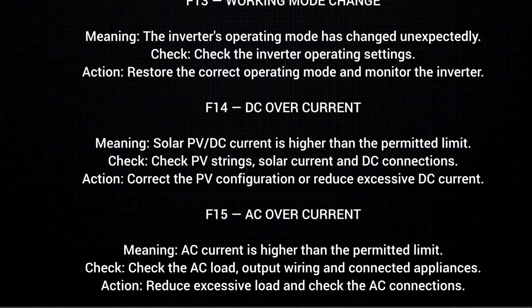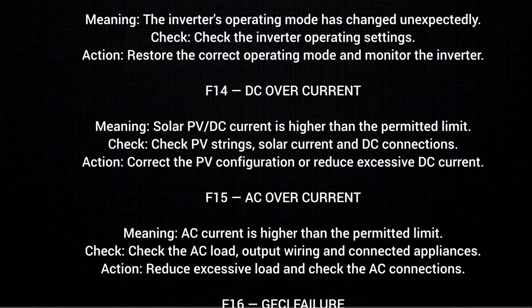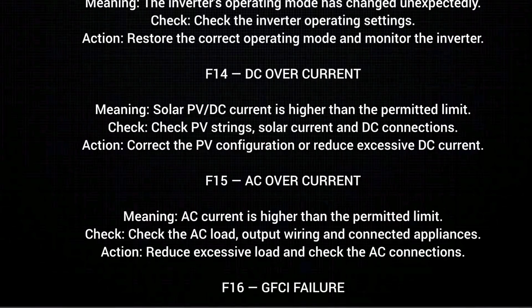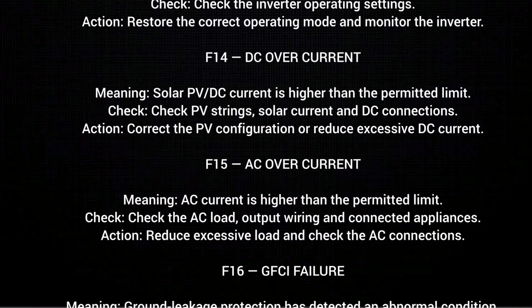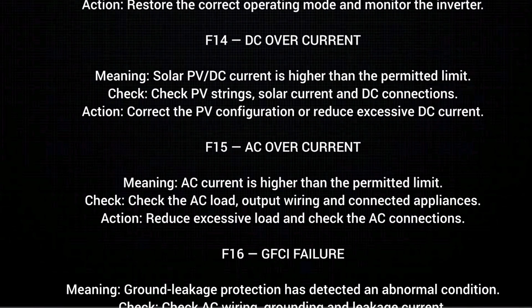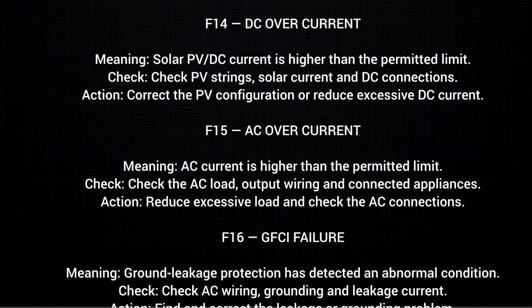F14 DC overcurrent, meaning solar PV DC current is higher than the permitted limit. Check. Check PV strings, solar current and DC connections. Action. Correct the PV configuration or reduce excessive DC current.